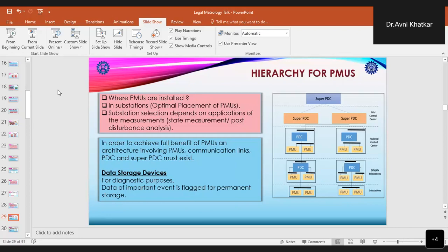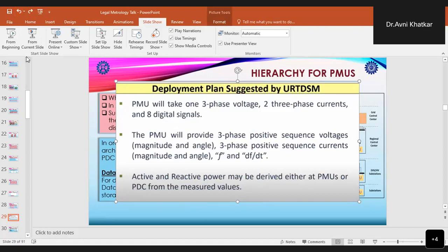And in order to achieve the full benefit of the PMUs, an architecture which involves the PMUs, communication links, and PDCs and super PDCs must also exist. As per the deployment plan strategy of URTDSM, PMUs were to be installed. They will take 1 three-phase voltage, 2 three-phase currents, and 8 digital signals. And then these PMUs will provide three-phase positive sequence voltages, both magnitude and angle, and three-phase positive sequence currents, both magnitude and angle, the frequency and change of frequency. And active and reactive power may be derived either at the PMUs or at the PDCs from the measured values.